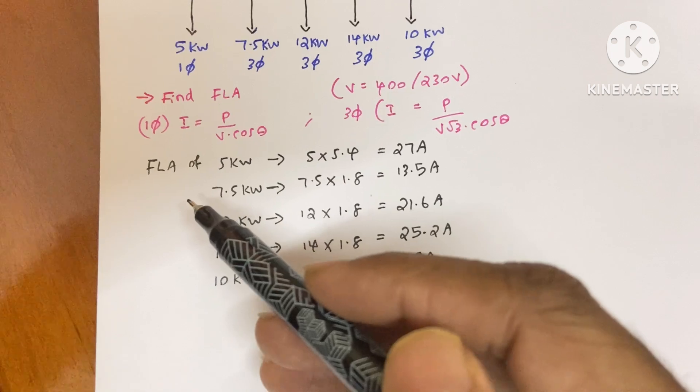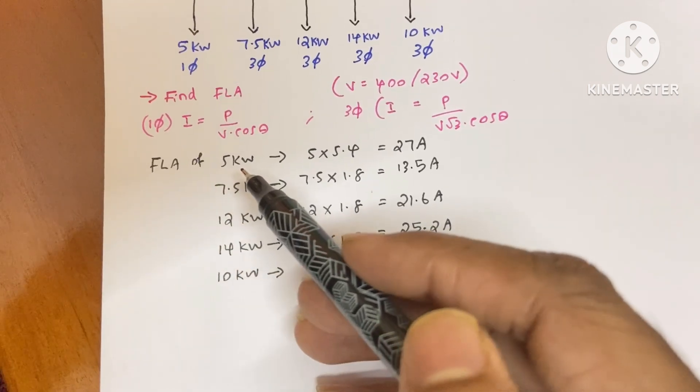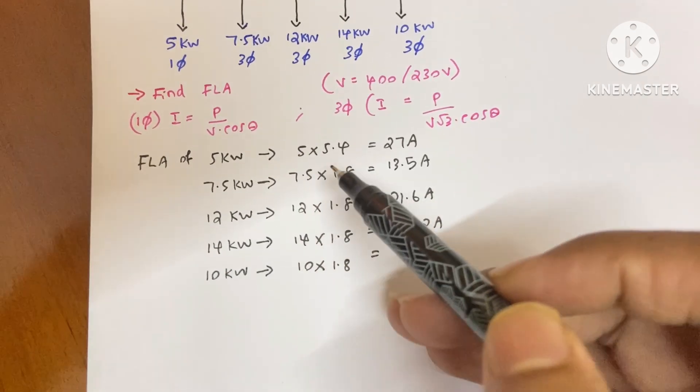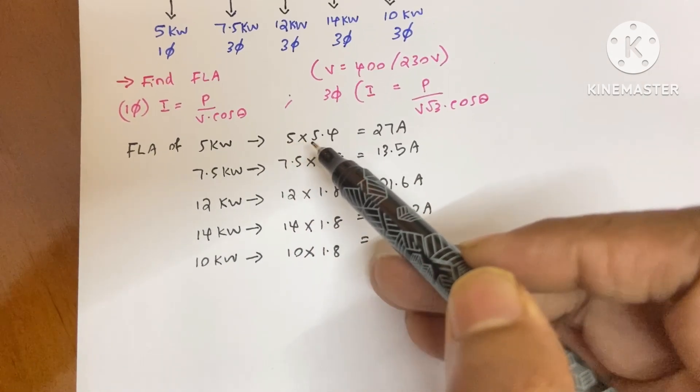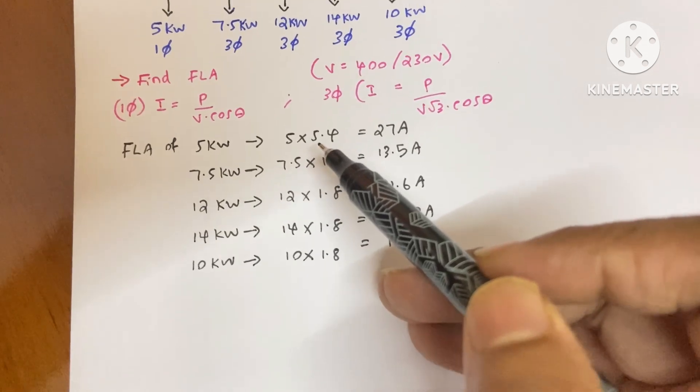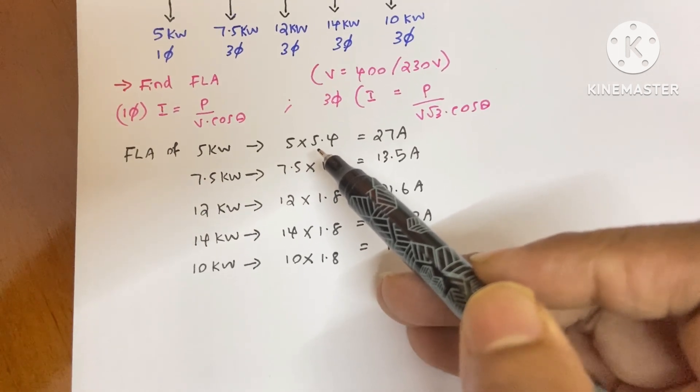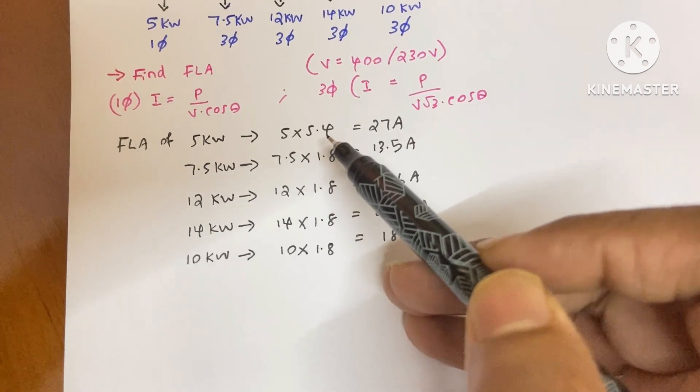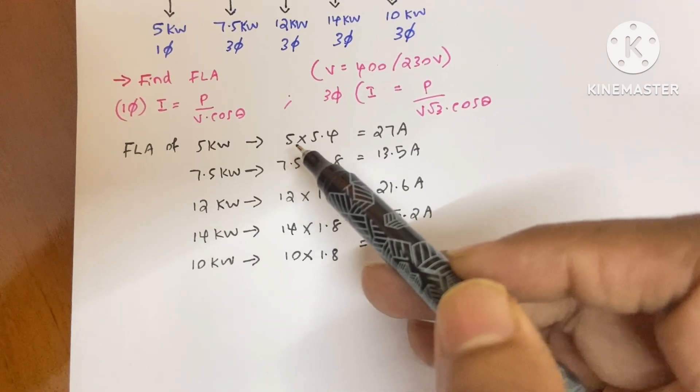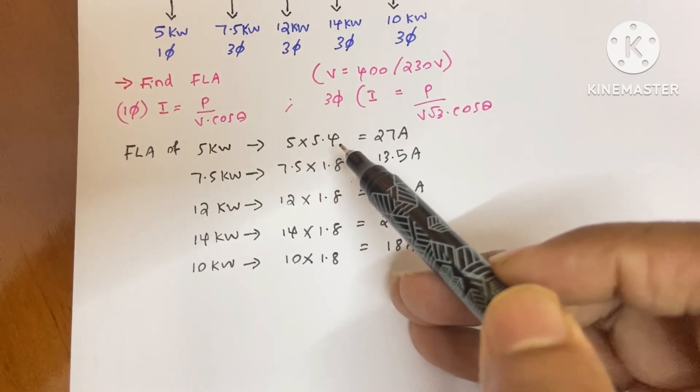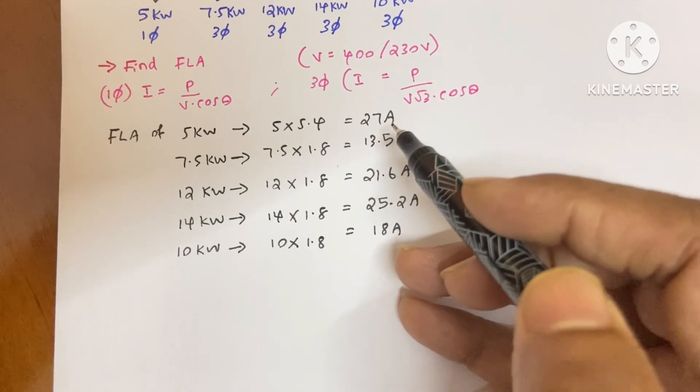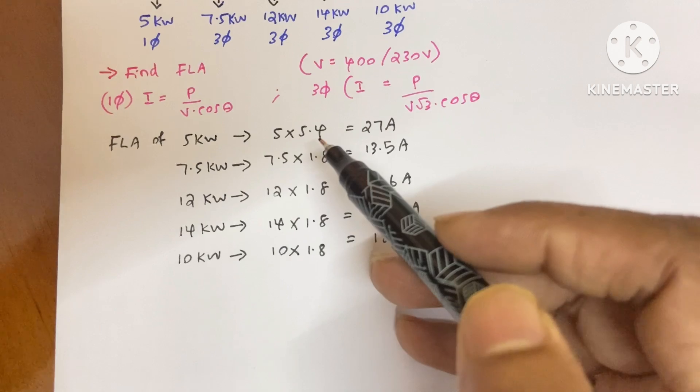Now we are going to find the full load ampere of the 5 kilowatt single phase motor. So here, 5 kilowatt into 5.4. We have a shortcut method here. If the motor is single phase, then we multiply the kilowatt with 5.4, then we will get 27 ampere. It is the full load ampere using this shortcut method.